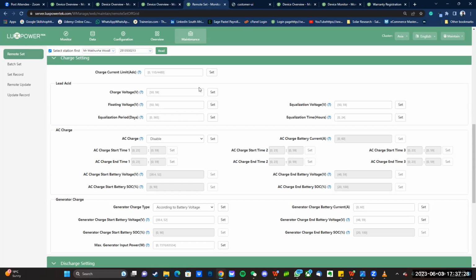But if you have a lithium battery and the BMS is not too reliable at the moment, and you're experiencing a lot of battery voltage high warnings, what you can do is with our new firmware update, I think it was a couple of months ago, Luxpower released a new firmware update where after you update that unit, you can bypass the lead acid settings.